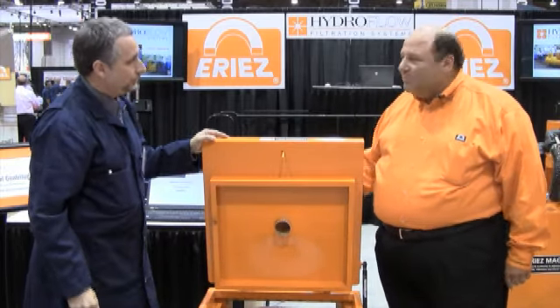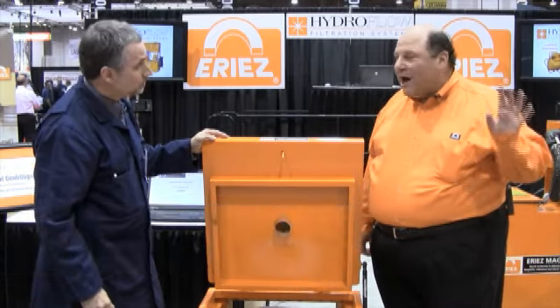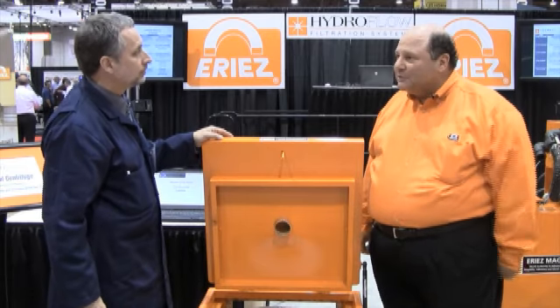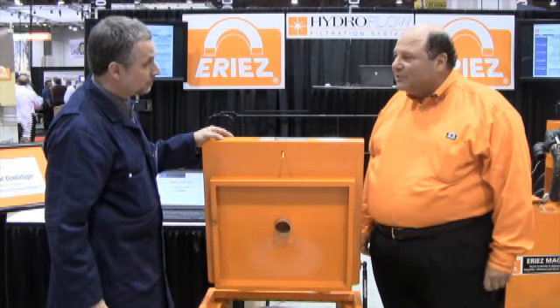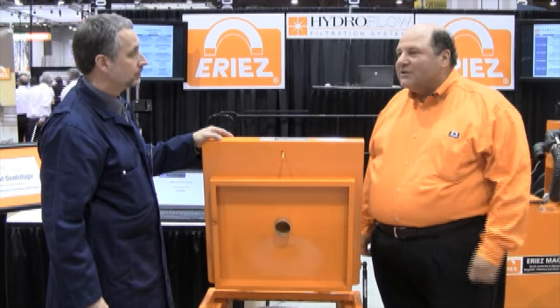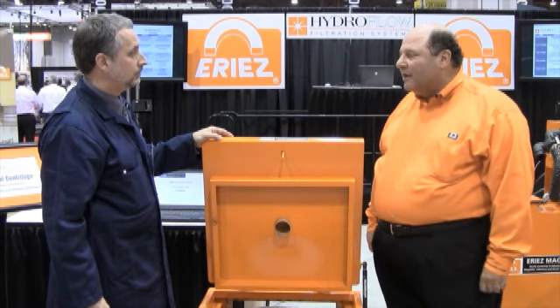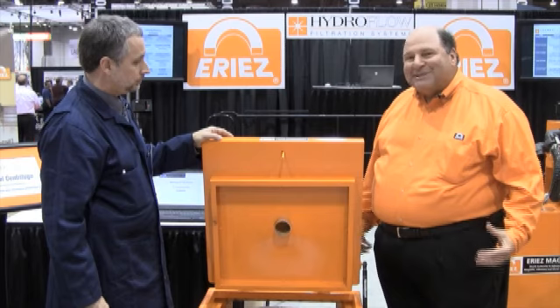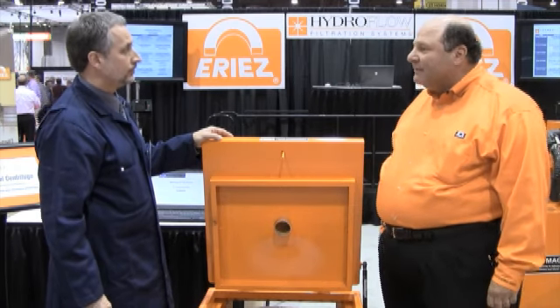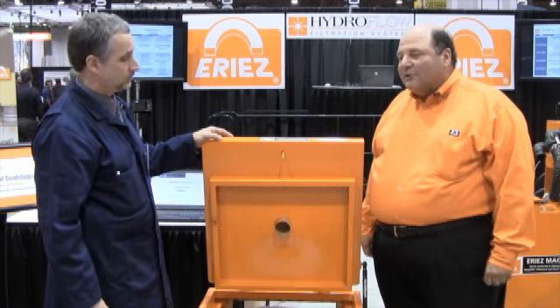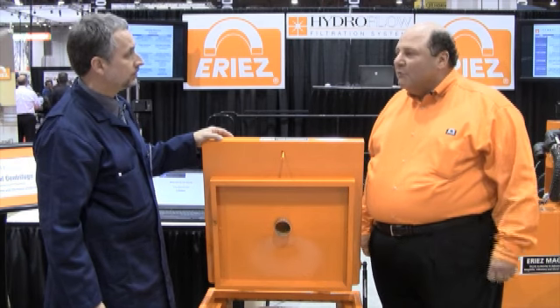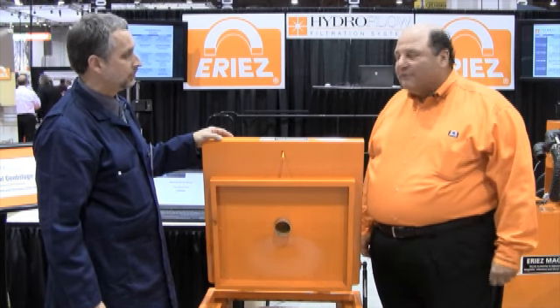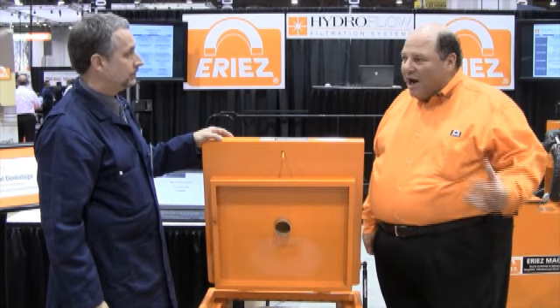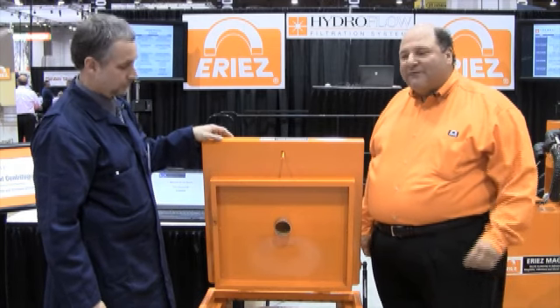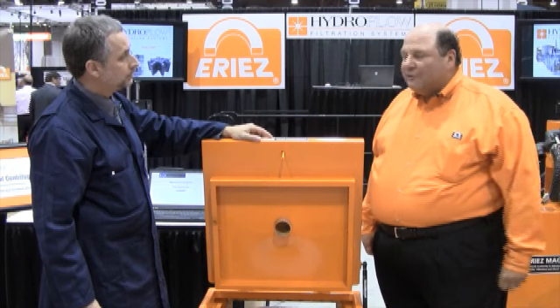This is a single bowl, low speed centrifuge. It's a liquid solid centrifuge, compared to a high-speed disc bowl centrifuge, which is a liquid-liquid centrifuge. This particular unit is rated at 20 gallons a minute on water soluble fluids, 15 gallons a minute on oils. It's ideal for filtering solids out of grinding swarf, grinding with ceramic material, removing glass from grinding operations, the wire drawing industry, and other industries needing fine filtration at fairly low flow rates.